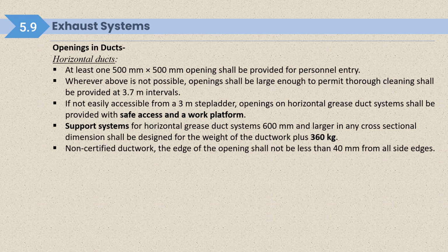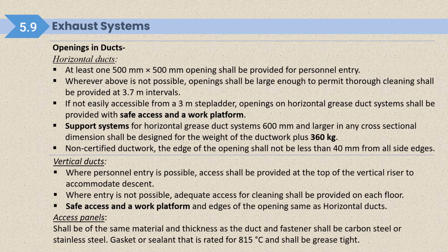For non-certified ductwork, the edge of the opening shall not be less than 40 mm from all side edges. So whenever we are connecting two portions of the duct, the edges should not be less than 40 mm from all sides. For vertical ducts where personnel entry is possible, access shall be provided at the top of the vertical riser to accommodate descent of the person who is going to enter into the duct. Where entry is not possible, adequate access for cleaning shall be provided on each floor. Safe access and work platform and edges of the opening are the same as horizontal ducts, like 40 mm of edges, and safe access and work platform if it is not accessible by a 3-meter step ladder.